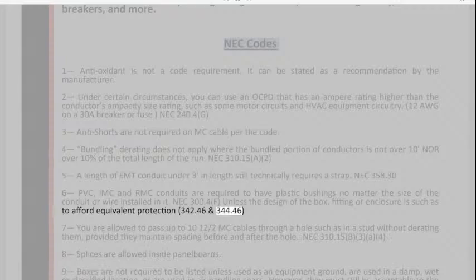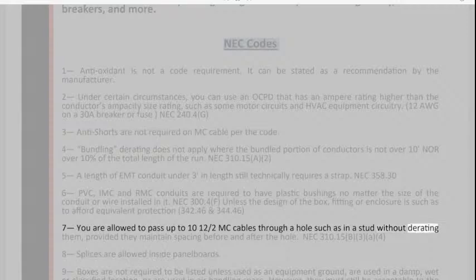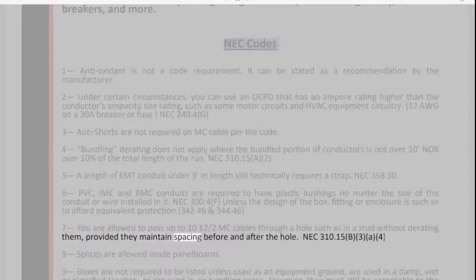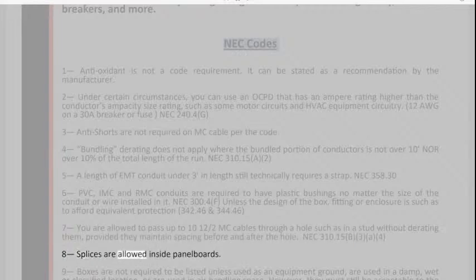344.46. 7. You are allowed to pass up to 10 12/2 MC cables through a hole such as in a stud without derating them, provided they maintain spacing before and after the hole. NEC 310.15B3A4.